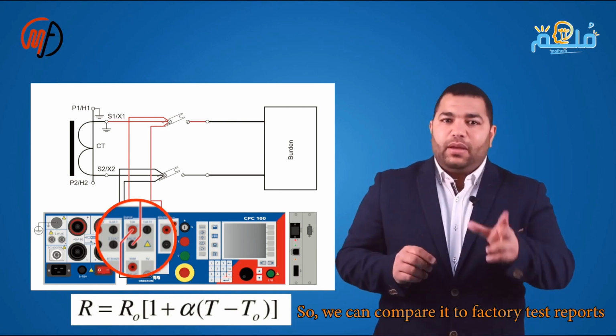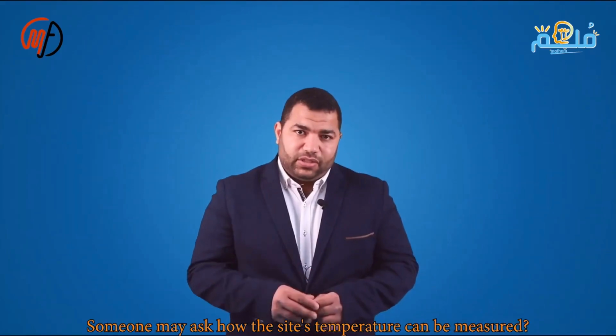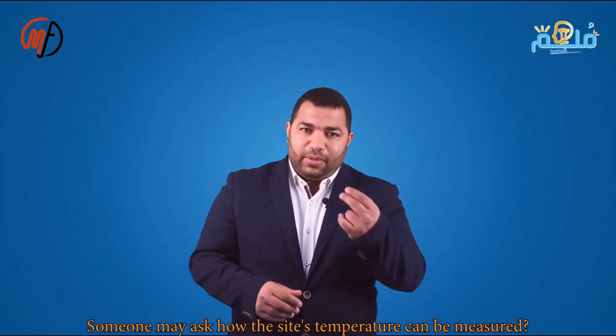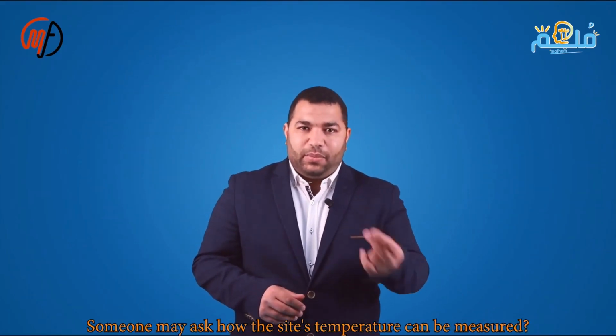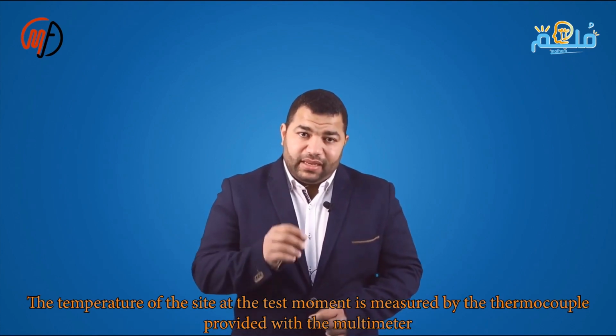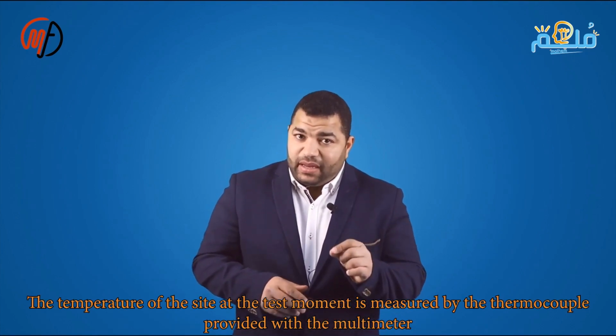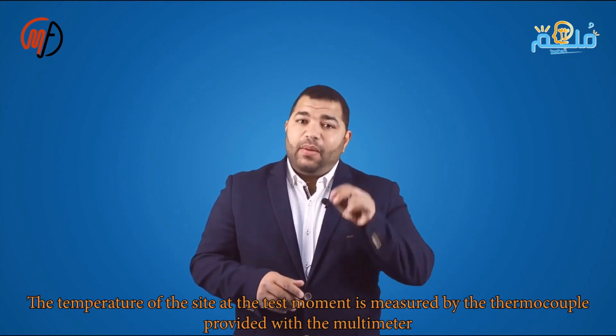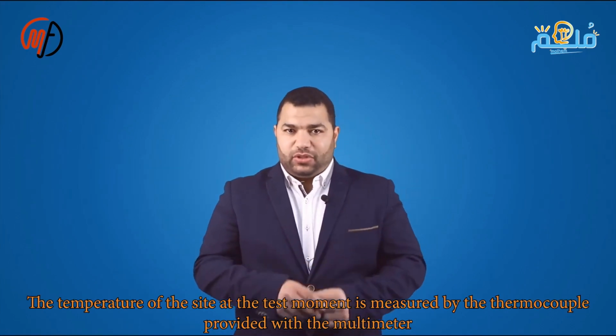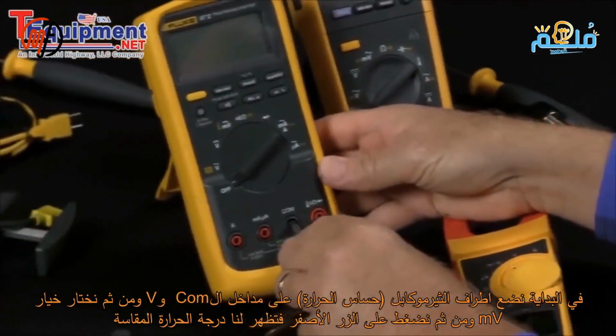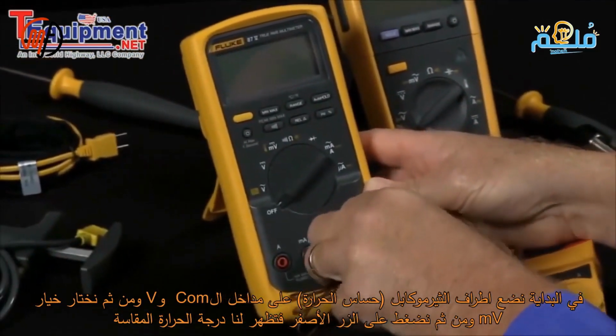The site temperature at the time of the test is measured using the thermocouple that comes with the Fluke multimeter. You will connect it to the Fluke multimeter, switch the meter to the millivolt setting where you will see a thermometer icon, then press the black button, and we are now continuously comparing the readings. To switch between Fahrenheit and Celsius, we will press the black button.